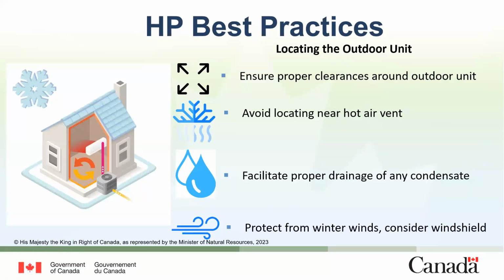Beyond sizing, installation of the unit is also important for good performance. In NRCan's recent field trials, several best practices were found to have a big impact. When installing the outdoor unit: ensure proper clearances around it, avoid locating near hot air vents, facilitate proper drainage of condensate, and protect from winter winds with a windshield if needed.